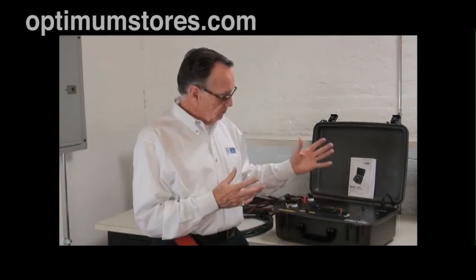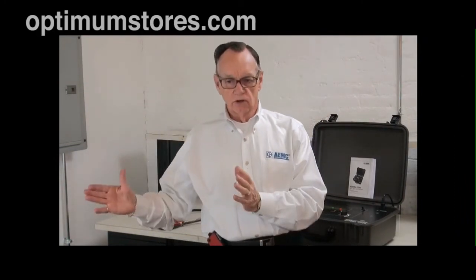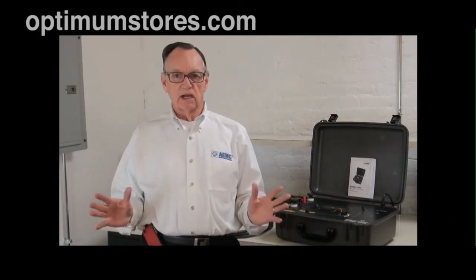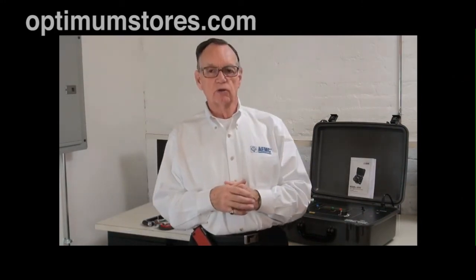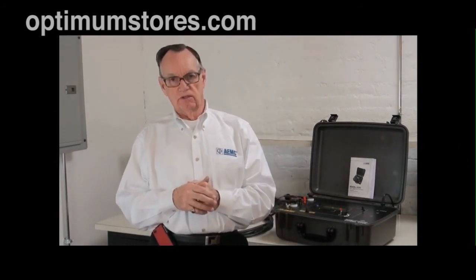So to summarize, we have a device that is now fully adjustable from 10 to 200 amps, with unprecedented accuracy down to 0.1 microohm resolution. We have USB connection now with the DataView software package for a tighter listing of our readings, and we have long leads available up to 50 feet.